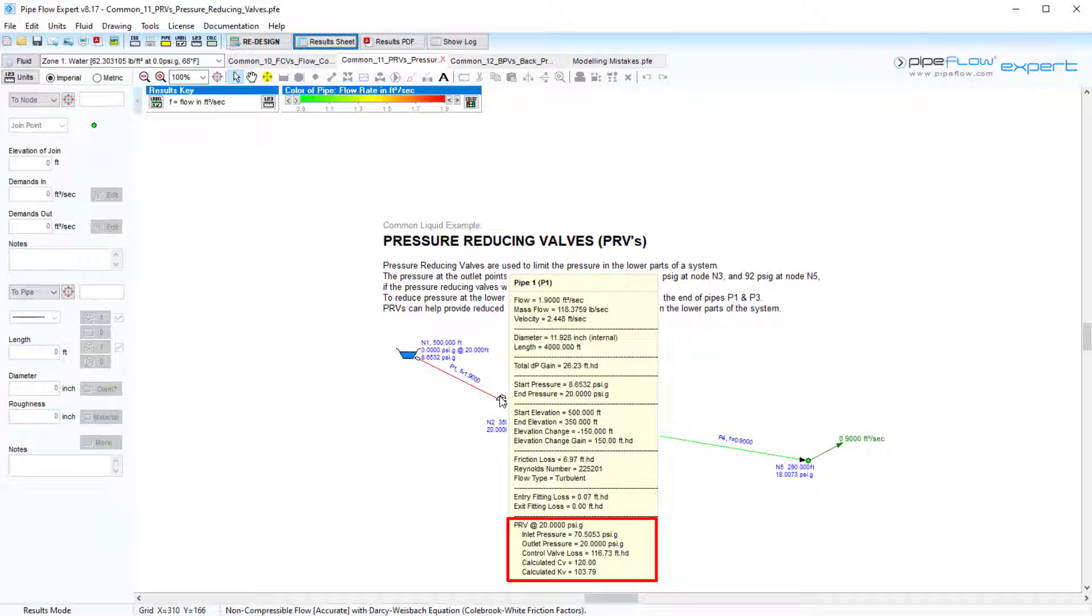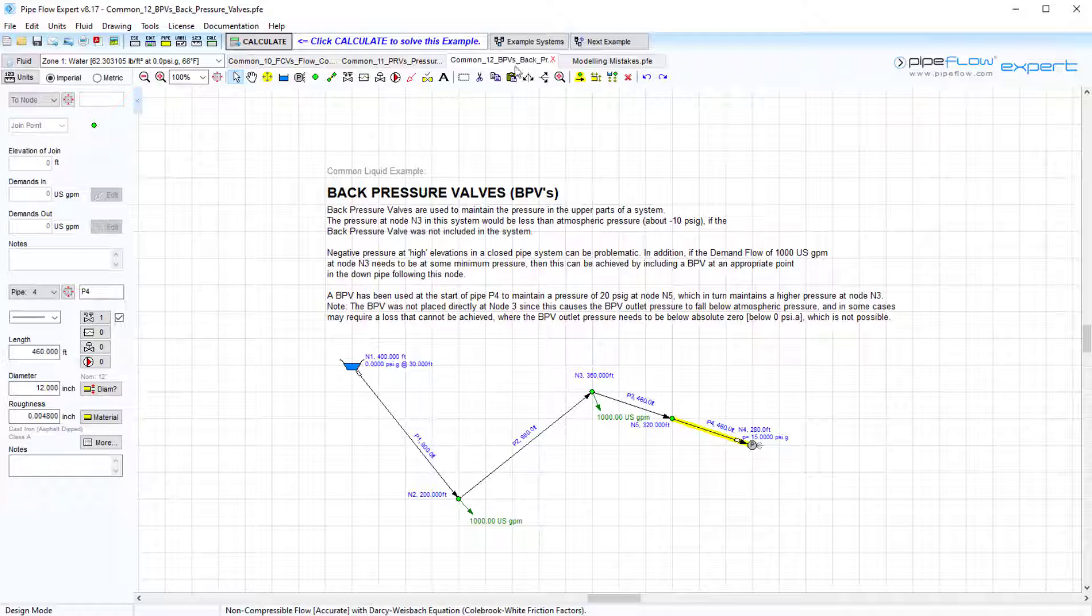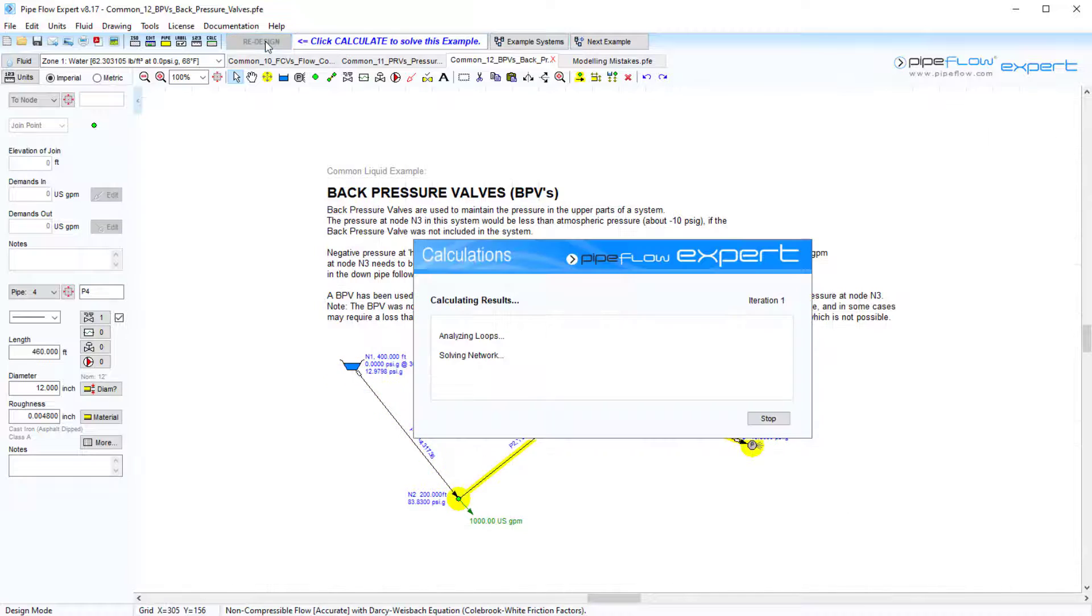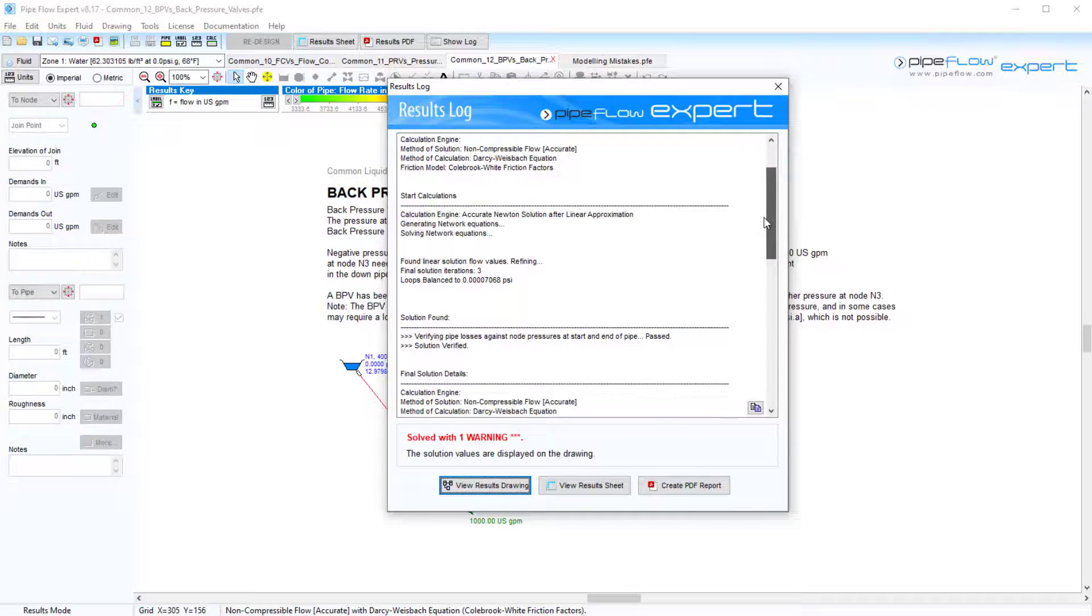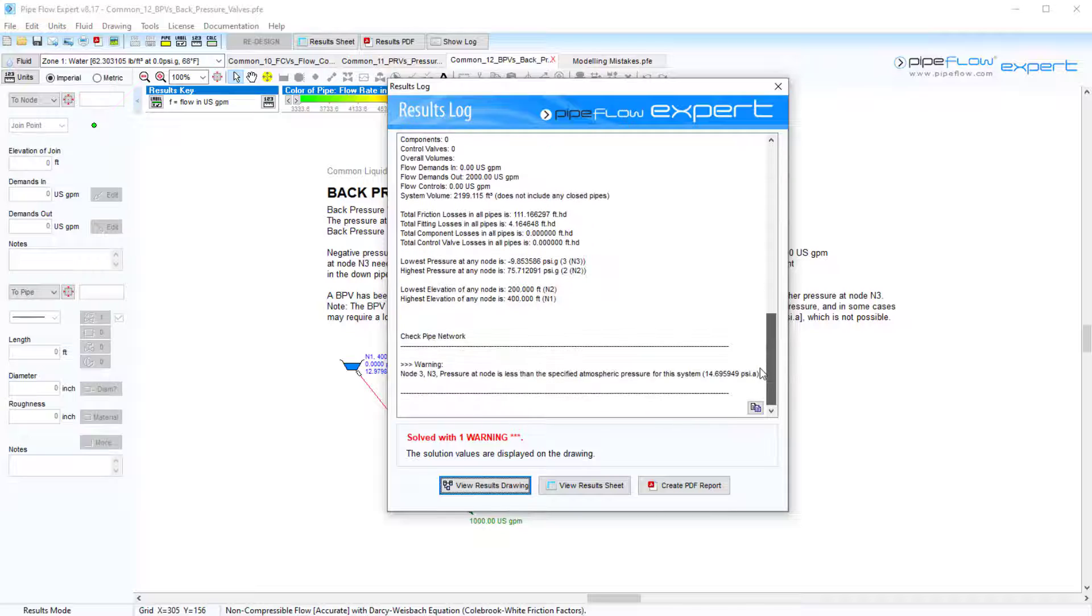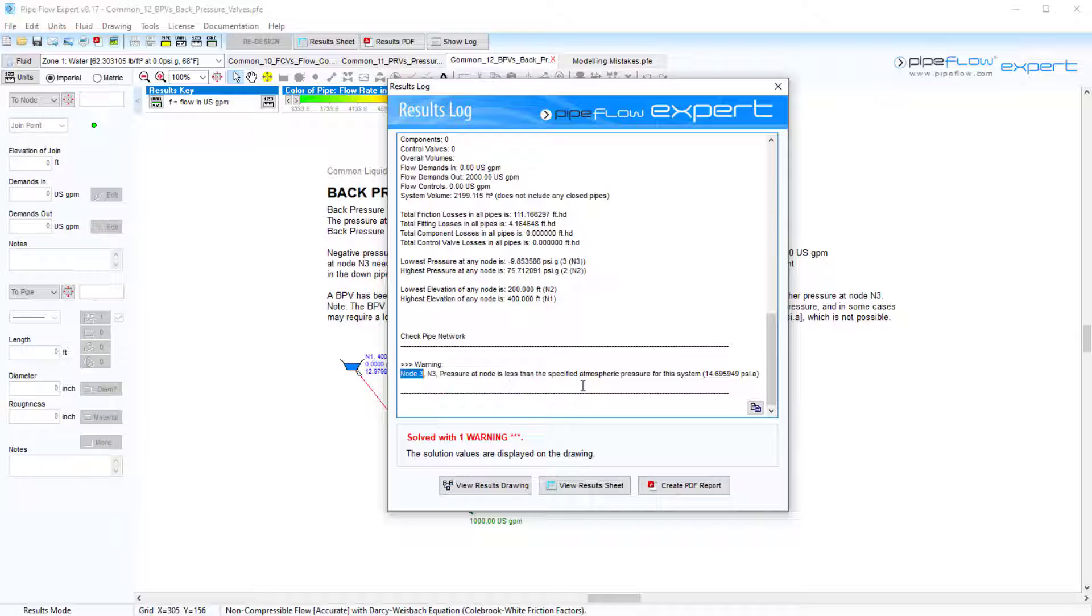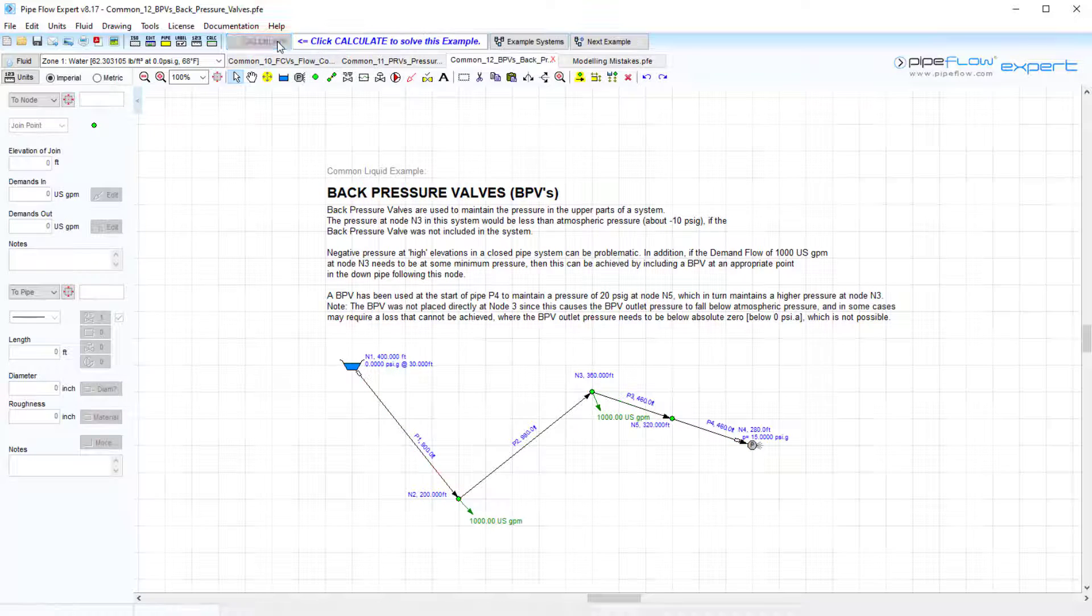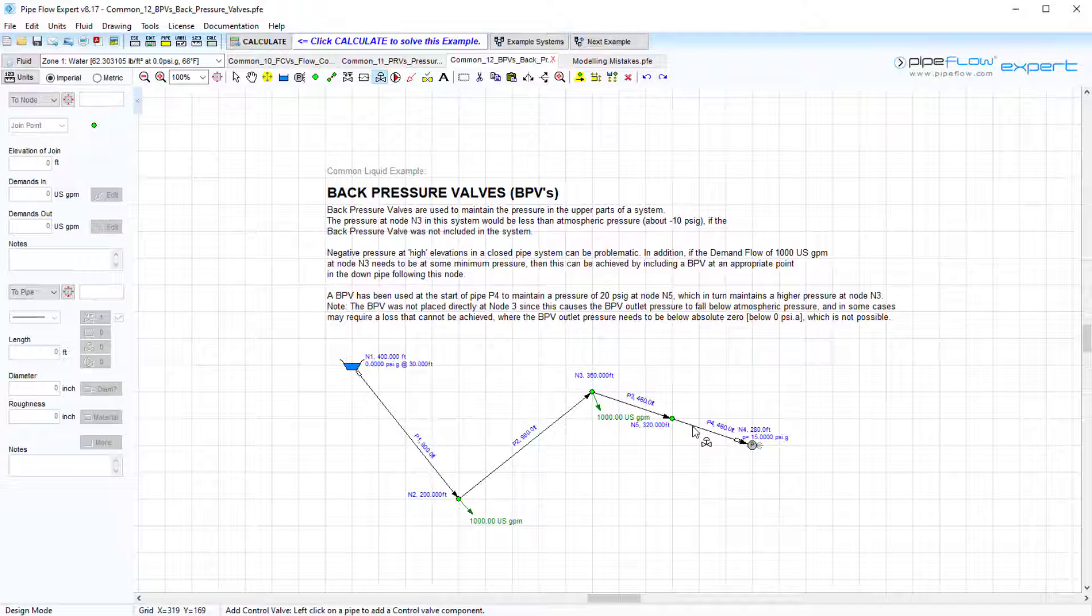Back pressure valves are used to maintain the pressure at the start of a pipe by again introducing a pressure loss. Solving this example, we are presented with a warning in the results log which shows that the pressure at node 3 would need to be less than atmospheric pressure, which can be problematic if, say, we require a certain minimum pressure to deliver the 1000 US gallons per minute flow rate at this outlet.